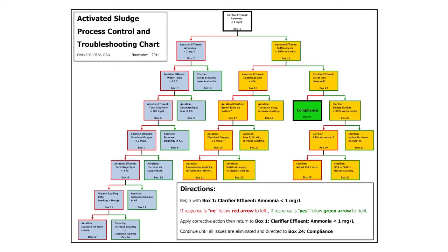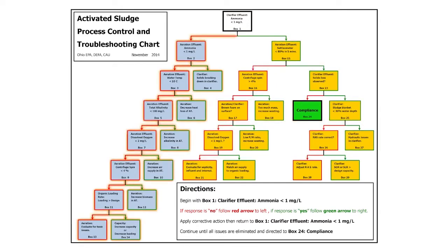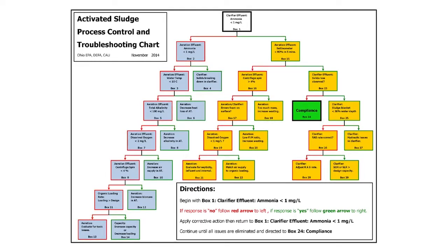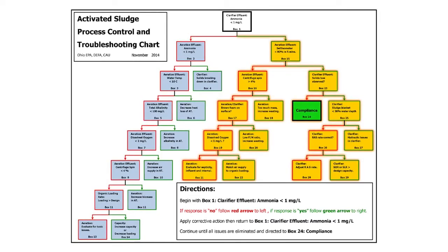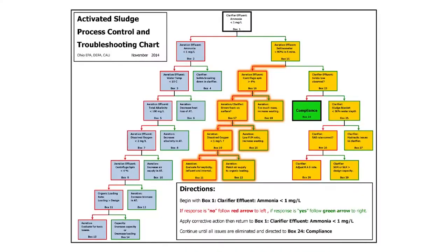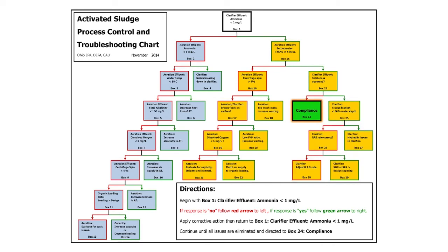So this is the flowchart. You start at the very top and it asks what is the effluent of the clarifier ammonia content. If the answer is yes, you go to the green side — the right side. If the answer is no, you go to the left, which is in red. You can see there are three main tracks. The blue tracks are the conversion issues. The yellow tracks are the separation issues. The separation issues are broken down into two other tracks: the middle track is if you grew the wrong kind of bacteria in the aeration tank — you grew filaments, which causes poor settling — and the track on the right is if you have clarifier problems. The goal is to get to the green box, which is compliance.